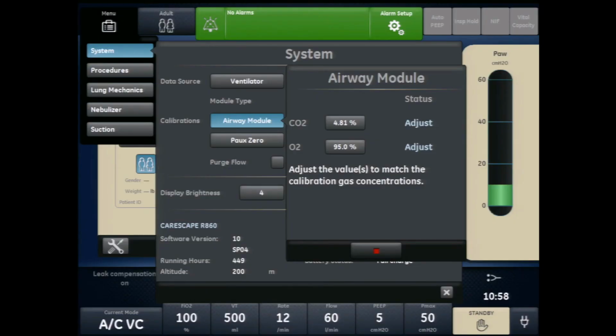If adjustments are needed, first select the gas to be adjusted. Use the trim knob to change the value until it matches the calibration gas cylinder value. Push the trim knob to confirm the change. And repeat for each gas requiring adjustment. Then select OK to exit.